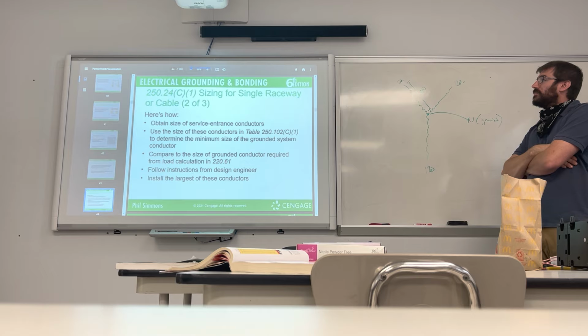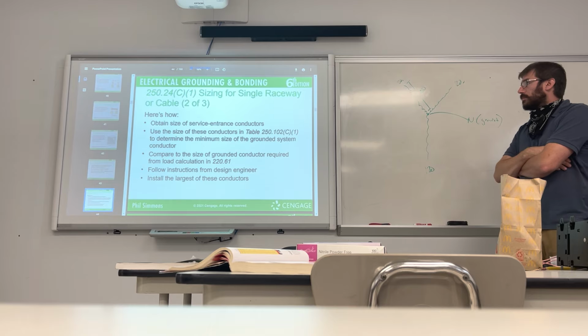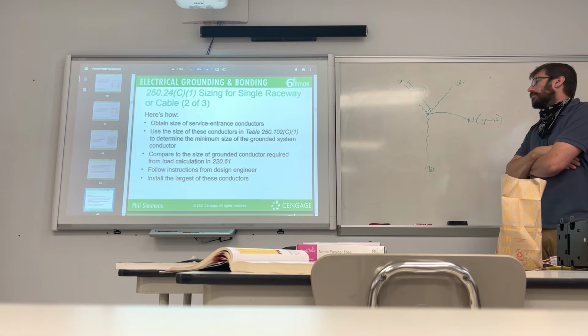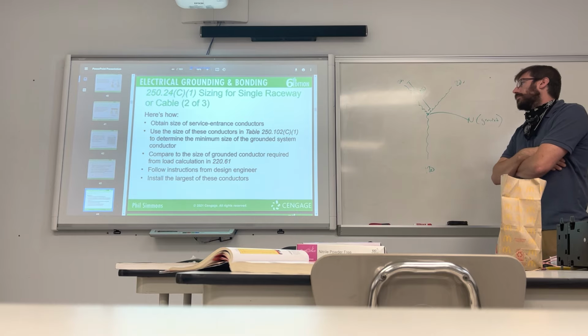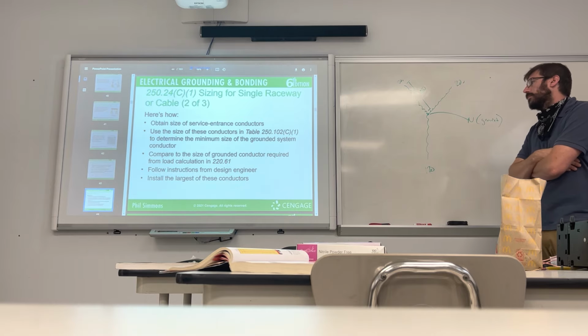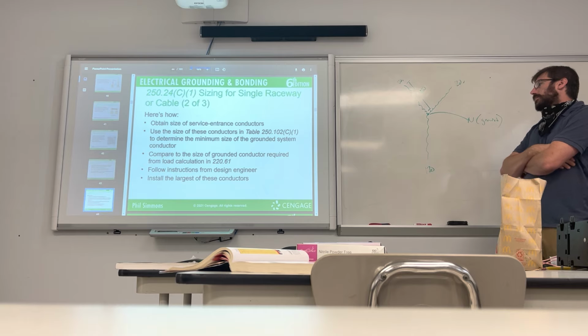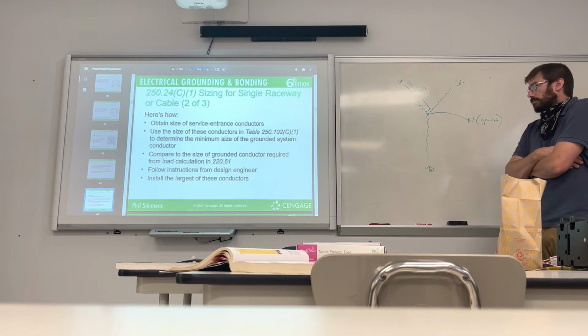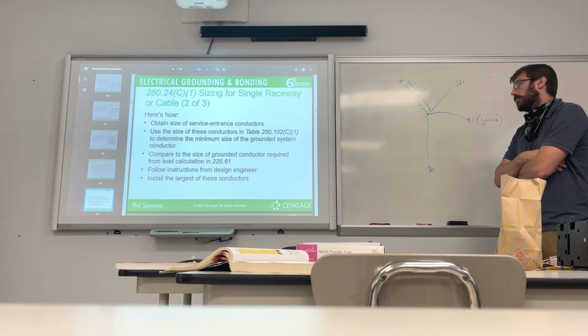250.24, sizing the single raceway or cable. Here's how. Obtain the size of the service entrance conductors. Use the size of these conductors in Table 250 to determine the minimum size of the grounded system conductor. Compare to the size of the grounded conductor required from load calculation in 220. Follow instructions from the design engineer. Install the largest of these conductors.